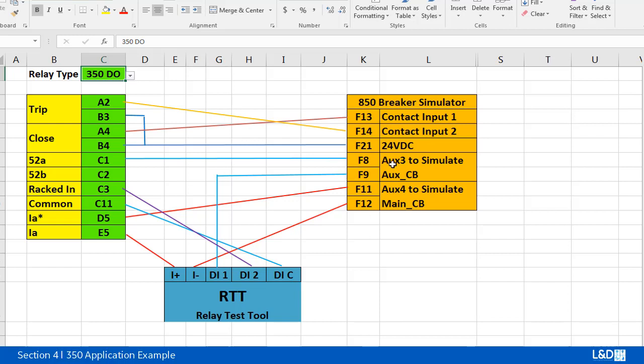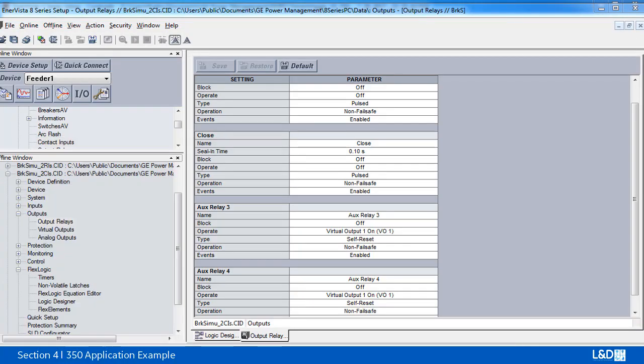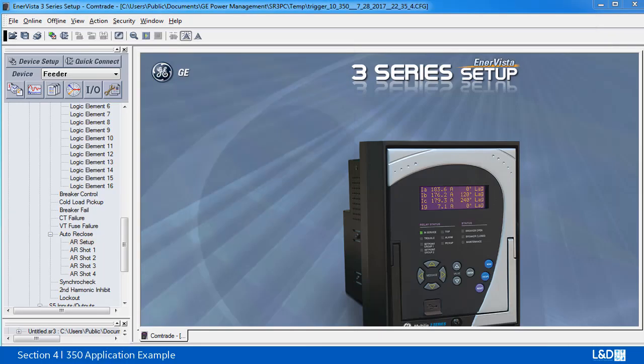That's the auxiliary 3 to simulate the auxiliary contact of the breaker. That's the status of the breaker. Then auxiliary 4 will be used to cut the AC current injected to the 350 relay. Okay, so now we're ready to do the test.